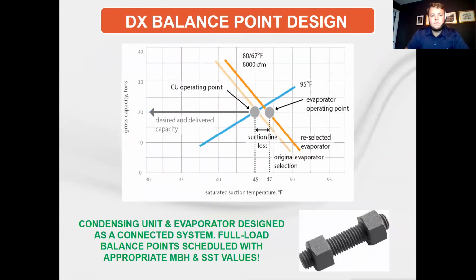So in this example, we have a balance point calculation showing how we take the evaporator curve and superimpose it onto the condensing unit curve. The way you do this is you run the evaporator at two different operating points. They may be 40-degree suction and 50-degree suction. Draw a line between those two points on the chart. One important thing is that in order for there to be flow from the evaporator outlet to the condenser inlet, there needs to be a pressure drop to force the gas from the evaporator to the compressor. The normally accepted range for that is about 5 psi, and with R410A, that's about 2 degrees Fahrenheit.